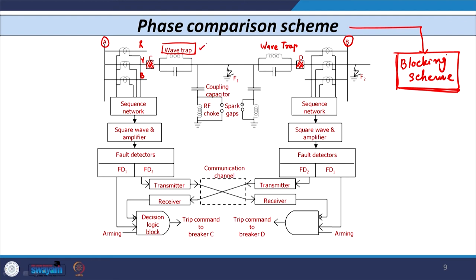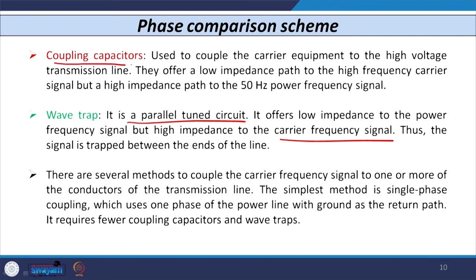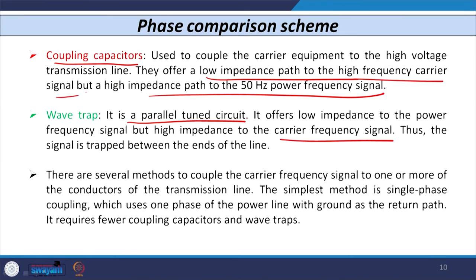A coupling capacitor also exists at both ends. Its working principle is exactly opposite to the wavetrap: it provides low impedance to the high-frequency carrier signal and high impedance to the fundamental 50 Hz frequency signal. So all carrier signals pass through the coupling capacitor to the associated equipment, while the 50 Hz power frequency signal is blocked.